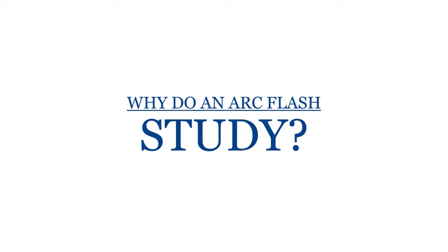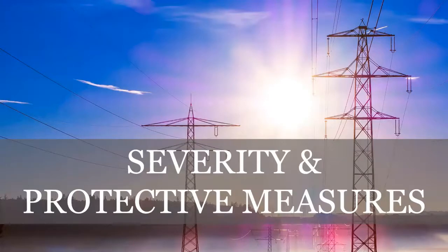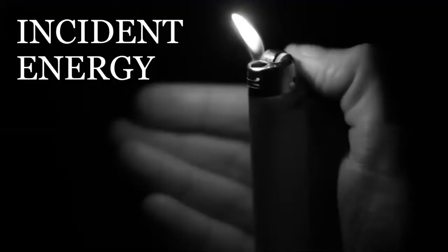So where does the arc flash study fit in, and why would we want to do one? Where it fits in is during that thought process, the 4 steps to determine the risk of any job. There's 2 of them where the arc flash study makes life a lot easier. The first one is when we're estimating the severity, and the second one is when we're trying to determine what PPE we need. So the arc flash study gives you a value, and it's called the incident energy. And the incident energy is essentially a measurement of how hot this arc flash can actually get. And typically it's measured in calories per centimeter squared.